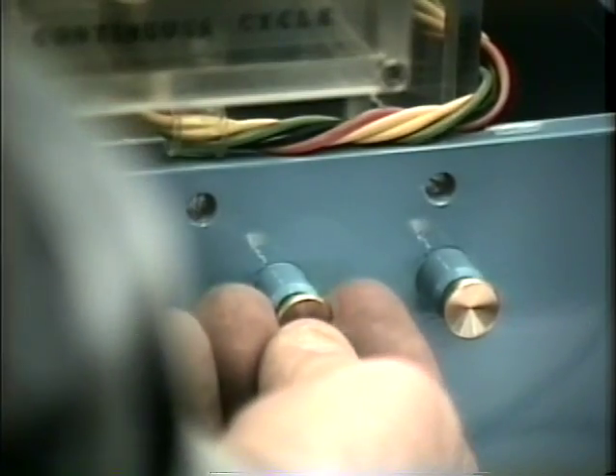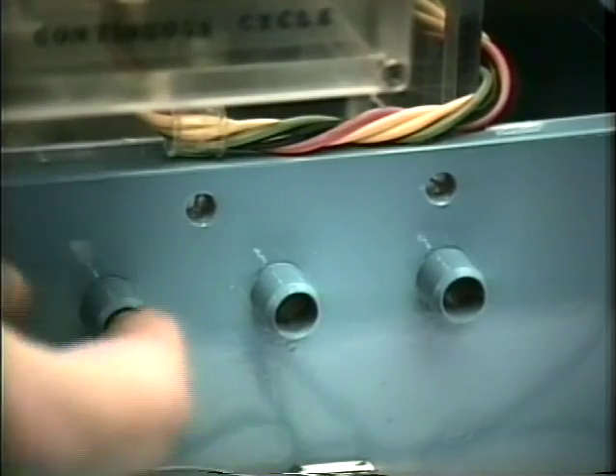When using the optional polishing equipment with the microtrim, plastic tubing is slipped over these 3 drain ports on the right side of the machine. It's essential to use tap water when doing the polishing operation. During normal operation of the microtrim, these ports must be closed by using the plugs as shown here.